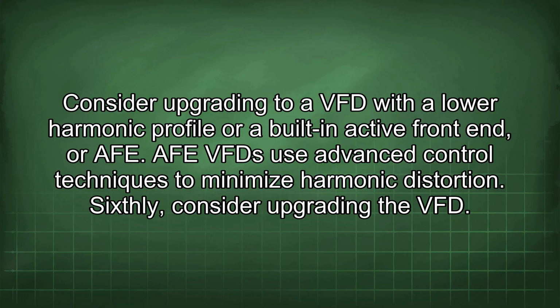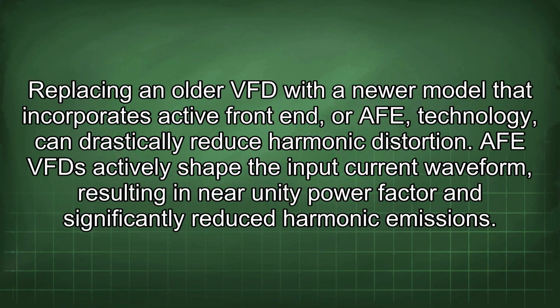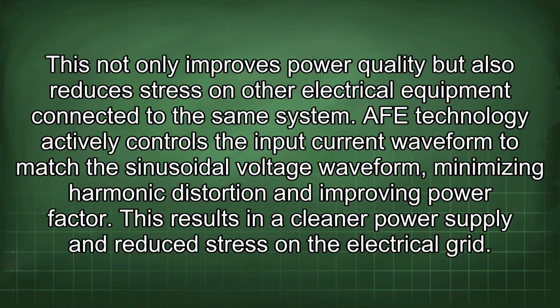Sixthly, consider upgrading the VFD. Replacing an older VFD with a newer model that incorporates active front end, or AFE, technology can drastically reduce harmonic distortion. AFE VFDs actively shape the input current waveform, resulting in near unity power factor and significantly reduced harmonic emissions. This not only improves power quality, but also reduces stress on other electrical equipment connected to the same system.